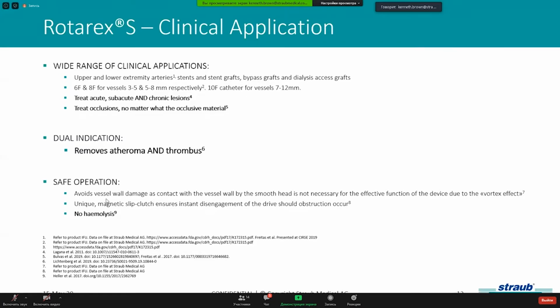Okay, we're not making contact with the vessel wall. We're using the inherent properties of a fastly rotating catheter to have the effect on the atheroma. So we're not cutting it out, okay, which has a disadvantage that we don't always clear all of the atheroma out of the vessel, but it has the big advantage that we're not causing vessel wall damage, because the devices that cut that atheroma out are non-specific. So you can cut out vessel wall as well if you're not careful.